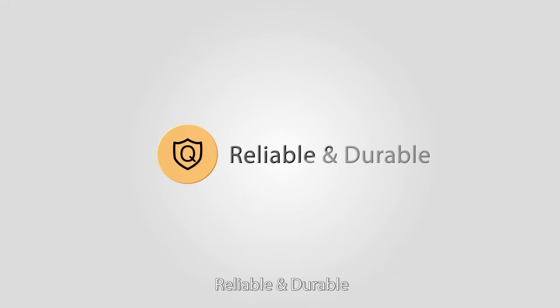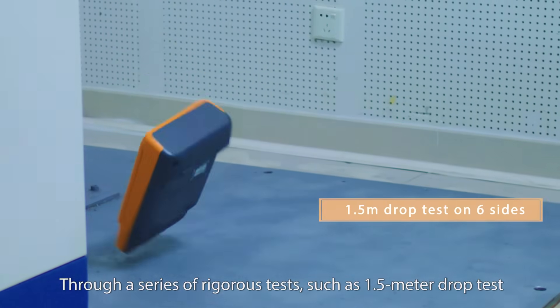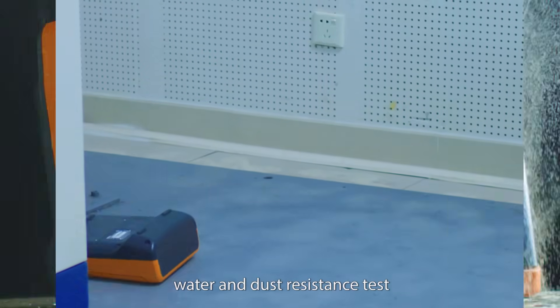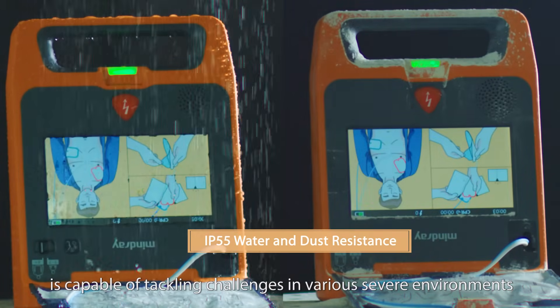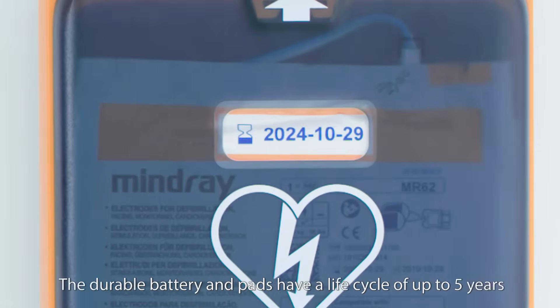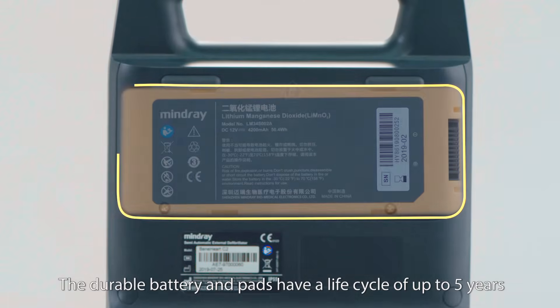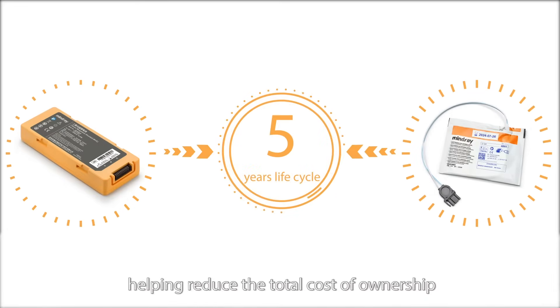Reliable and durable. Through a series of rigorous tests — including a 1.5-meter drop test and water and dust resistance test — confirm that the BeneHeart C-Series AED is capable of tackling challenges in various severe environments. It is equipped with high-quality consumables. The durable battery and pads have a life cycle of up to 5 years, helping reduce the total cost of ownership.